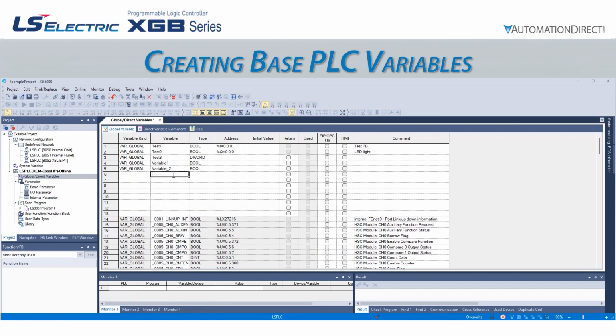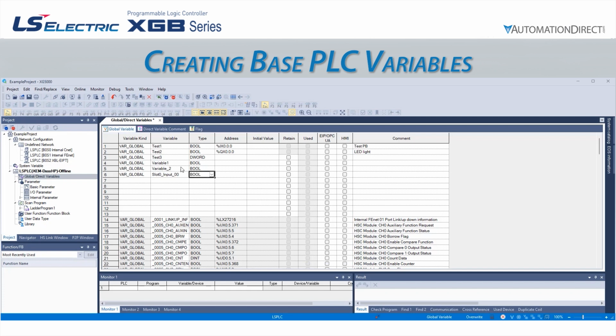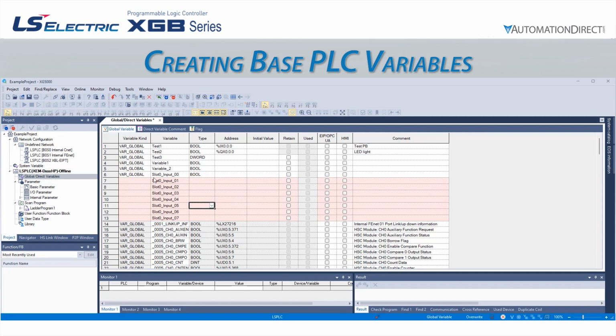If we create a variable called slot0_input_00 in the Global Variable tab, we can then use a spreadsheet-style click-and-drag copy function to have the software automatically index the variable number as it moves down the lines. This also applies to any direct variables we assign, as well as variable kinds and types. These are all extremely useful tools for creating variables, and especially similarly named variables quickly and easily.